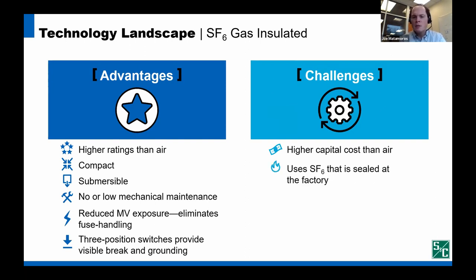Even though medium voltage gas insulated switchgear is generally sealed at a factory and does not require gas maintenance or cylinder handling like high voltage breaker applications, there are efforts to phase out SF6 for medium voltage and high voltage for sustainability and regulatory reasons. And while there are no federal regulatory actions underway to phase out SF6, California aims to phase out SF6 by 2031 for medium voltage applications and 2033 for high voltage applications.